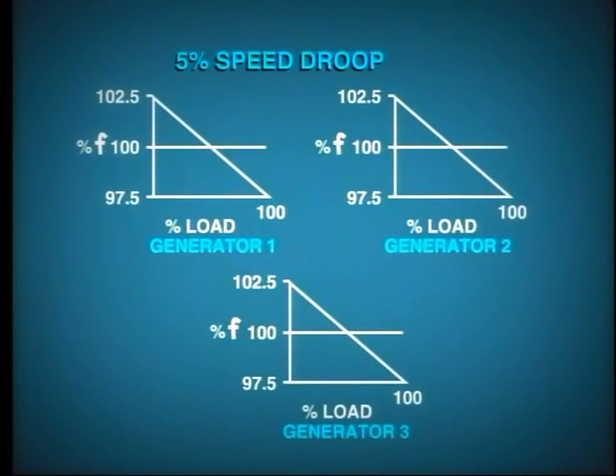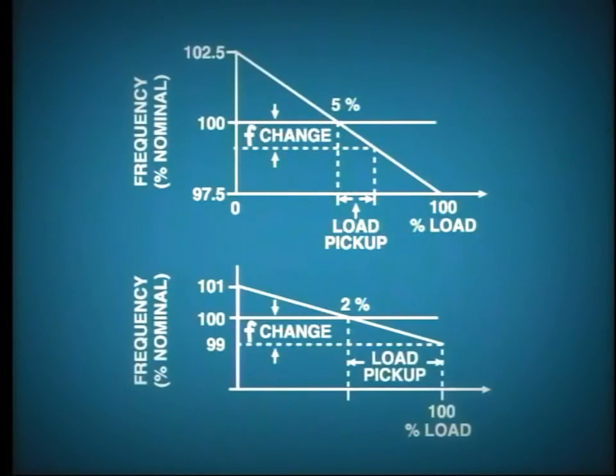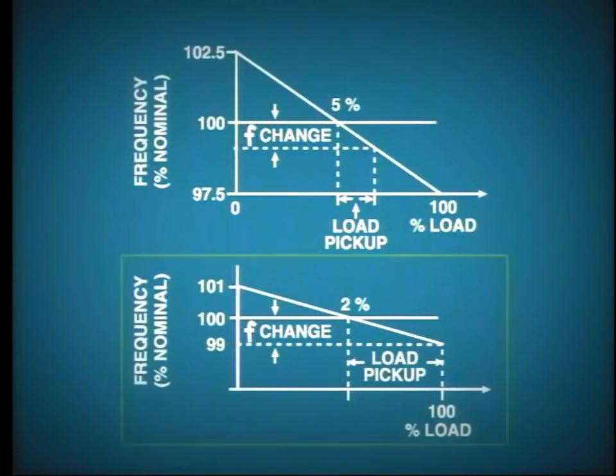If all of the governors on the synchronized generators are set to, say, 5% droop, then they all share in load changes proportionally. However, we may wish to make certain units on the system more responsive to frequency changes than others. This can be achieved by setting the droop characteristic on those units to a lower value. The generator with the lower setting will pick up or throw off proportionally more load than the other generators on the system. Check with your supervisor for correct droop settings on your machines. Remember, the lower the percentage droop, the more sensitive is the governor, and oversensitivity can cause unstable operation and hunting of the unit.